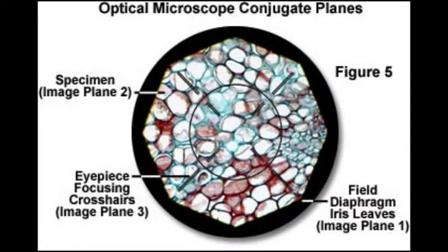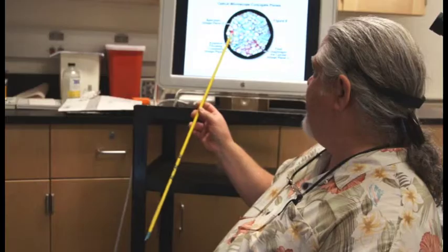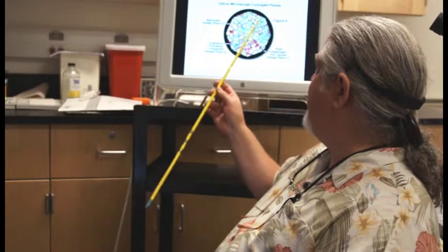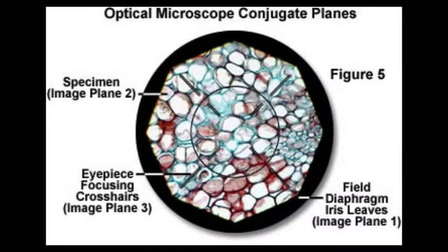And that looks something like this. Here you see your field of view, you see your specimen in focus, and you see the leaves of the field diaphragm centered to the field of view and highly in focus.